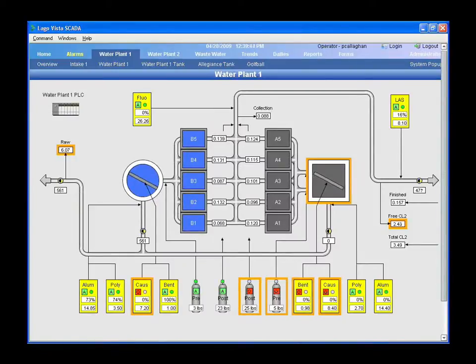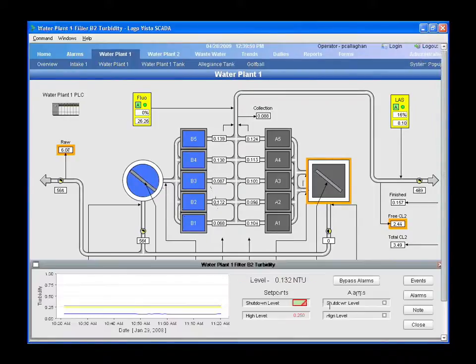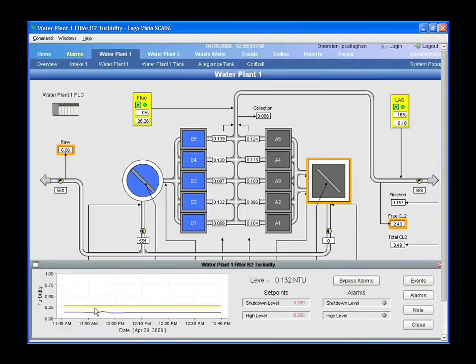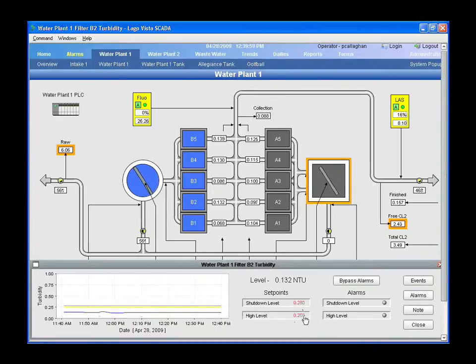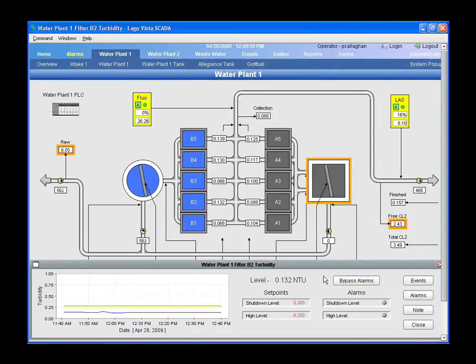This is a conventional upflow clarifier. We record turbidity — this is a runtime trend of the actual turbidity. This is a setpoint that the operators can change, and they can bypass it if needed so the system won't show an alarm if they're doing calibrations on the analyzer.